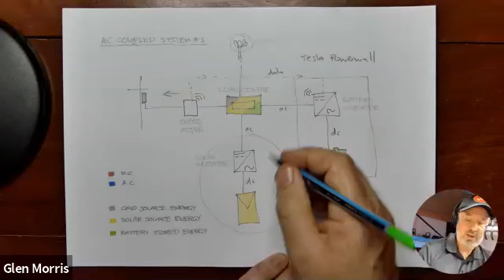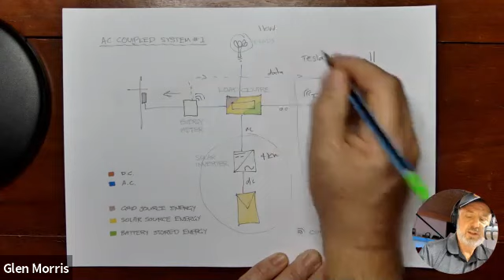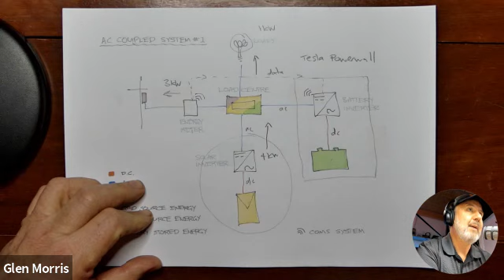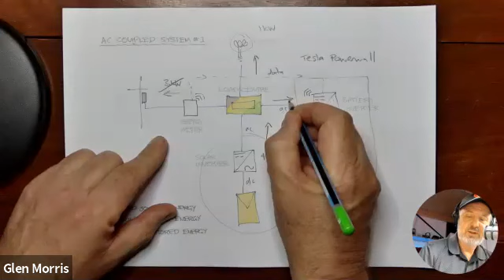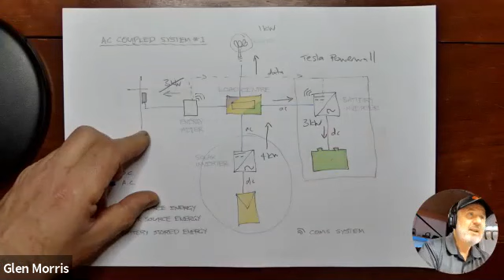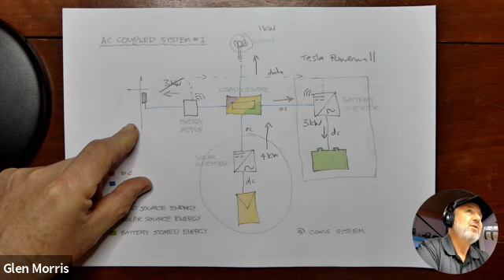So let's say it's the middle of the day, and this inverter is putting out 4 kilowatts of AC power. The loads are consuming 1 kilowatt of AC power, so 4 kilowatts this way, 1 kilowatt to your home. That means we're going to have the difference of 3 kilowatts flowing out to the grid. And so there's an opportunity to capture that. Now, this doesn't happen instantaneously. Generally, there's a ramp up of 10 to 30 seconds or so where the battery inverter sees that surplus opportunity and starts to charge its battery up to 3 kilowatts. So what it'll do is reverse that, so the extra 3 kilowatts is going into the battery system here and charging until the battery is full. So that's the charge process.